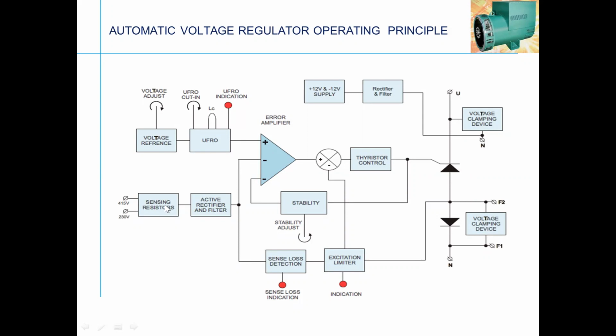Again, for measuring the voltage, whether the voltage drop is there, there is a sensing circuit. If you see, when we are crossing the signal, there is a policeman over there. So the sensing circuit, he will keep monitoring us when there is a down in the voltage, like a policeman, he gives, no, you are coming down, so increase the voltage. So like that, this is a sensing circuit which has been done, and the active filters which have been put across for filtering some noise or another thing. So this is a stability part, sense loss, excitation limit. So overall, this excitation will be given to the exciter, to the AVR, wherein it gives the excitation system. So this is something indication gives, and it has been controlled by thyristor, and the latest designs have come up with IGBT to reduce the noise.